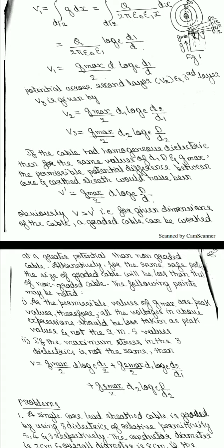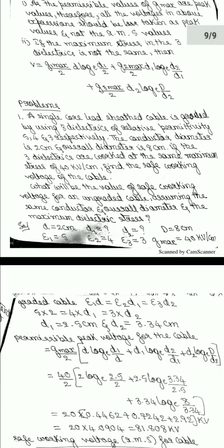Problems, we shall go for the problem. Okay, first problem: a single core lead sheath cable is graded by using 3 dielectrics of relative permittivity, they have given 5, 4, 3 respectively. The conductor diameter they have given 2 cm and overall diameter, that means capital D, they have given 8 cm. If the 3 dielectrics are worked at the same maximum stress of 40 kV per centimeter, find the safe working voltage of the cable. What will be the value of safe working voltage for an underground ungraded cable, assuming the same conductor and overall diameter and the maximum dielectric stress?